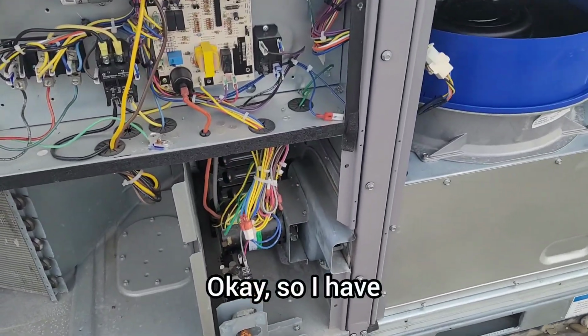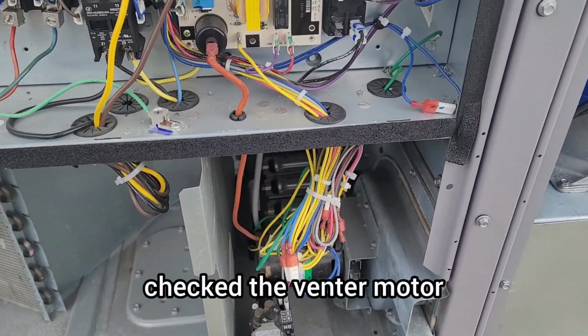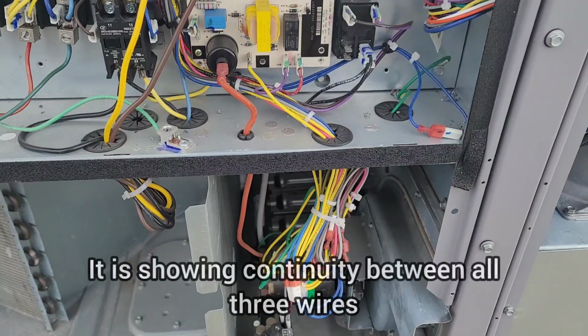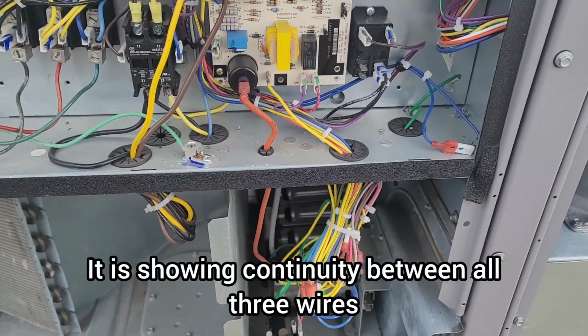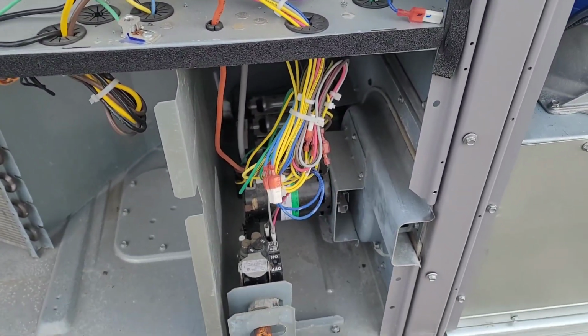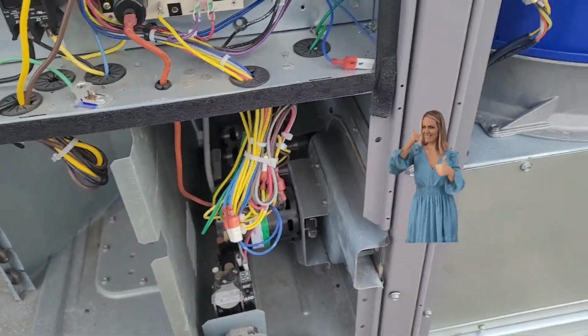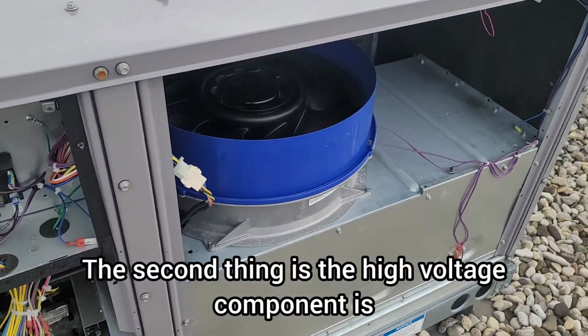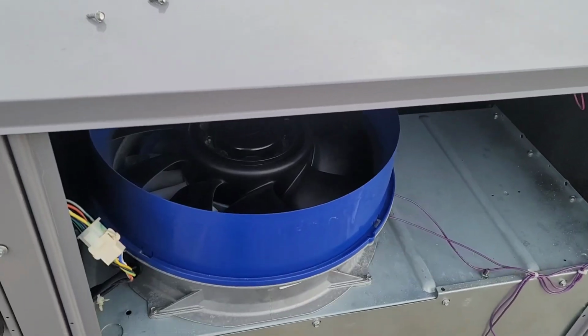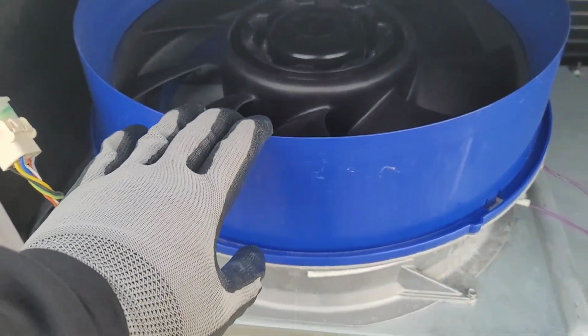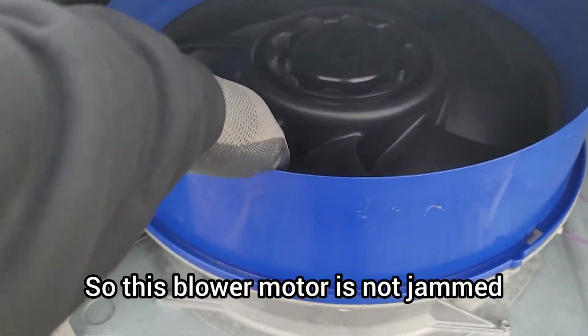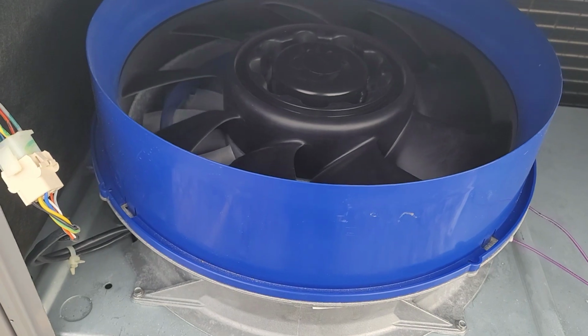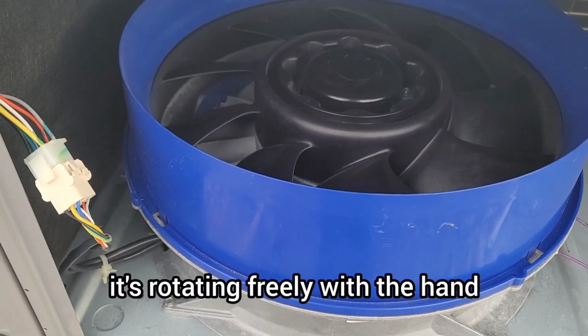Okay, so I have checked the venter motor. It is showing continuity between all three wires. So looks like our venter motor is okay. The second high voltage component is the blower motor. This blower motor is not jammed, as you can see. It's rotating freely with the hand.